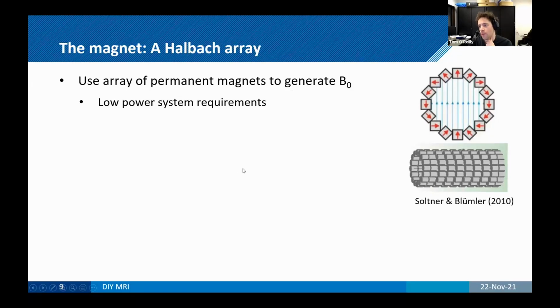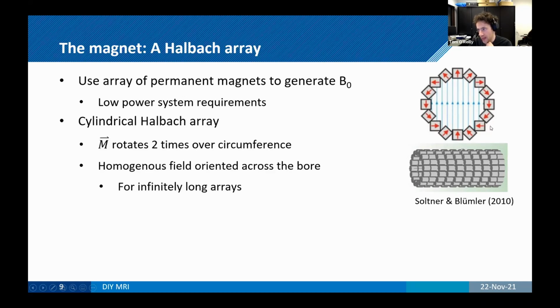So for those who don't know, a Halbach array is one of the yokeless magnet designs. It basically uses a whole array of magnets to produce a homogeneous magnetic field inside of the cylinder. So to do that, you have your individual magnets with the arrows indicating the magnetization, and that magnetization rotates twice over the circumference of the Halbach array. And that, in theory, for an infinitely long Halbach array with identical magnets, gives you a perfectly homogeneous field that is oriented across the bore of your magnet. So that's important to remember, because typical MRI scanners will use a solenoid-based approach to making the magnetic field, which means that the magnetic field is pointing down the bore of the magnet.